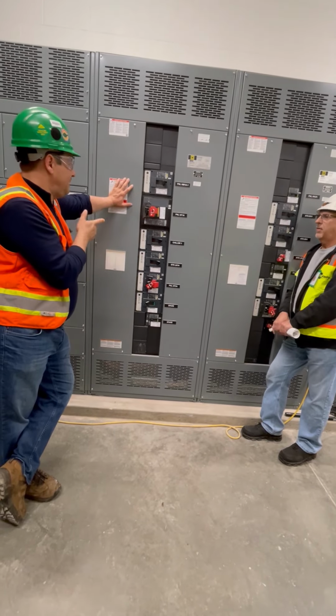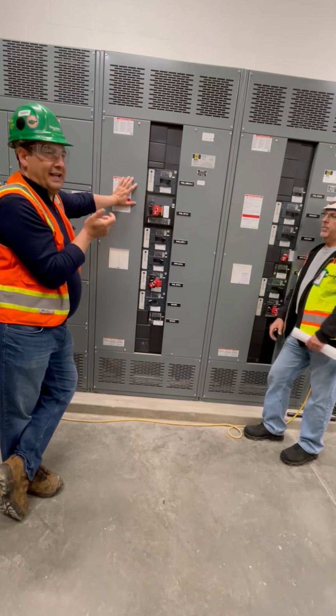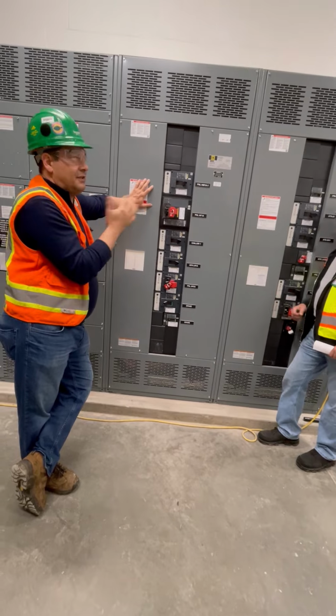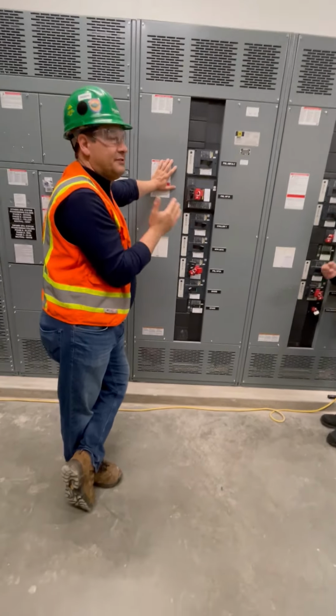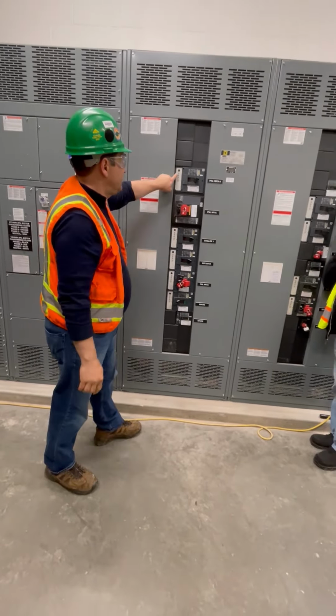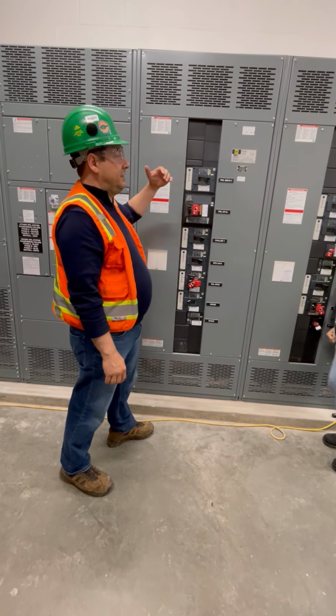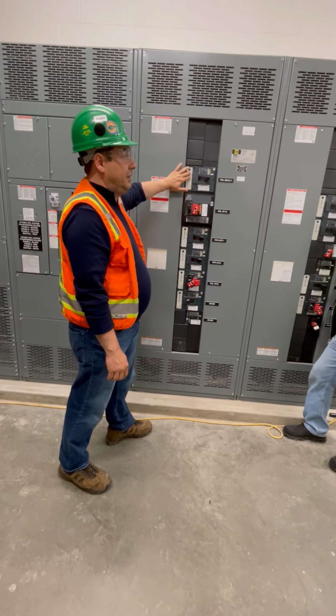But that's a good question, I missed that. It's a push to test mechanically, it's not a push to test. That tells you that the breaker still opens mechanically, right? That's really it. It doesn't test the electronic part of it, the true protection part of the breaker.